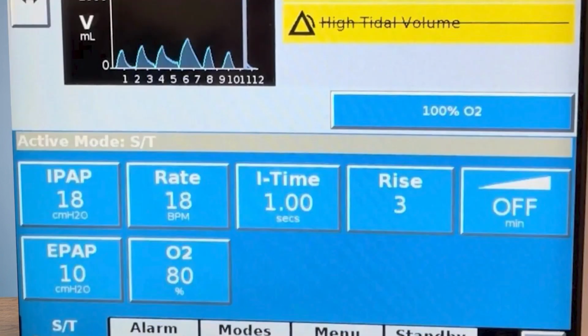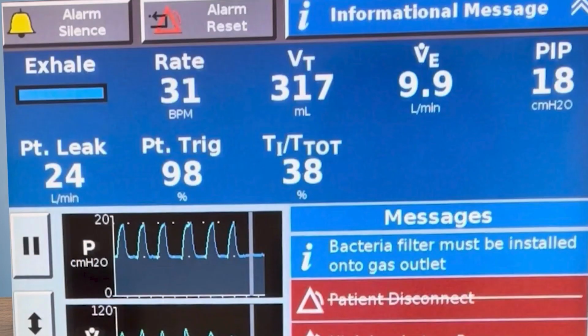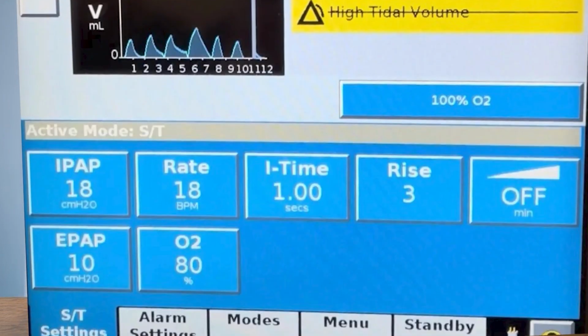Also, check out, there is a backup rate here set to 18 breaths per minute. Now, while BiPAP usually relies on patient-triggered breaths, most machines now include a backup rate to guarantee a minimum number of breaths even if the patient stops breathing or becomes apneic. Now, remember, the values at the top are the actual values, including the actual tidal volume the patient is pulling and the amount of leak, and the bottom values are the set values.